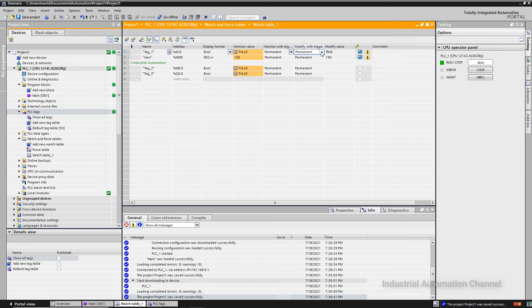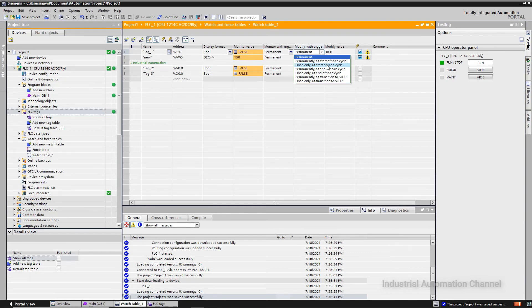If you open here you can see we have seven different triggers. 'Permanent at the start of cycle' will push your desired value at the start of your program and it will remain always in this value. The third one pushes your value only one time. 'Permanently at the end of program' pushes your value at the end of your program, always. The next one does it once only at the end of your program. The next one does it when your CPU goes to stop, and the last one is the same but done only once.